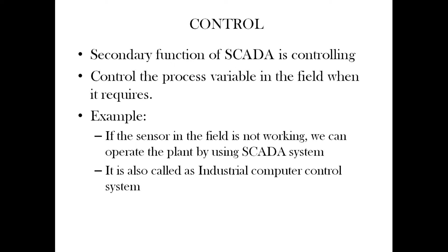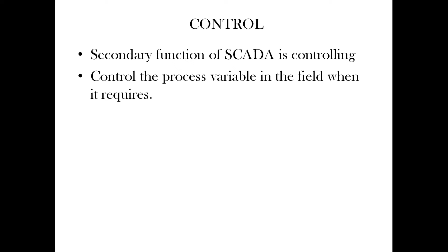For example, if the sensor in the field is not working, we can operate the plant by using the SCADA system. Imagine in the field we have the low level sensor, and imagine this is not working. If this is not working, how can a PLC turn on the inlet valve? Is it necessary to shut down the system for 4 to 5 hours to repair this low level sensor? It will affect my production, right? So I should have some option to take control from SCADA. Even though a level sensor is not working, I should be able to turn on the inlet valve. So, how are we going to do that?